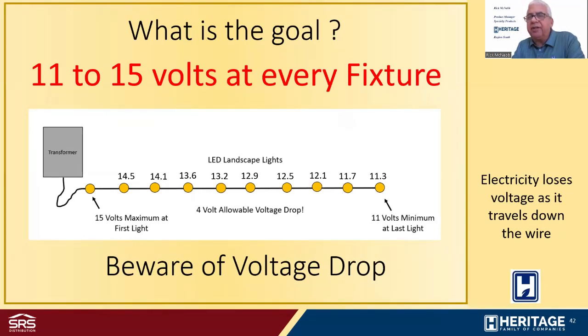So you can be confident that if you're using a UL 1838 professional outdoor lighting transformer, that first light will have no more than 15 volts. But if you notice here, as electricity travels down that wire from the first fixture down to the last, we have a problem with voltage drop. Voltage drop happens no matter what you do with the system. There's no way you can stop voltage drop. Now we can manage voltage drop, but we're definitely going to lose voltage from the transformer to that last fixture.